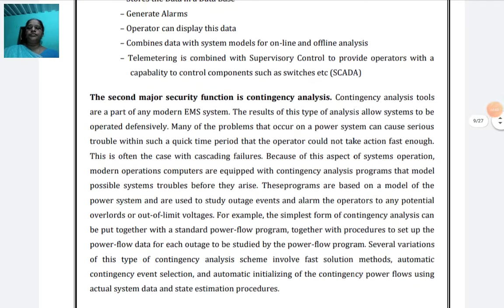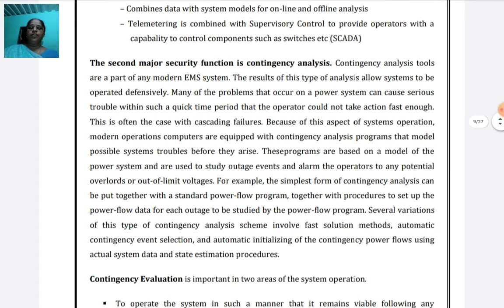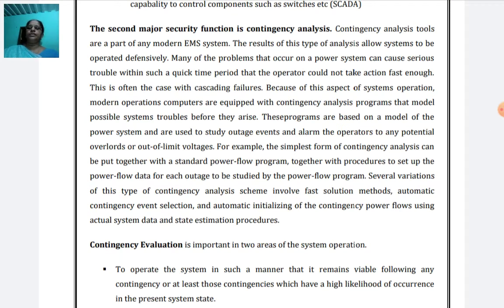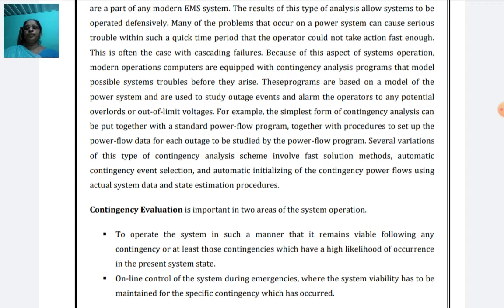Then the second major security function is contingency analysis. What is meant by contingency? A problem, an outage. Outage means line outage and generator outage. The contingency analysis tools are part of any modern EMS, that is, the energy management system. This contingency analysis can be put together with the standard power flow program, together with a procedure to set up the power flow data for each outage to be studied by the power flow program. Several variations of this type of contingency analysis scheme involve fast solution methods, automatic contingency event selection, and automatic initialization of contingency power flows using actual system data and state estimation procedures.